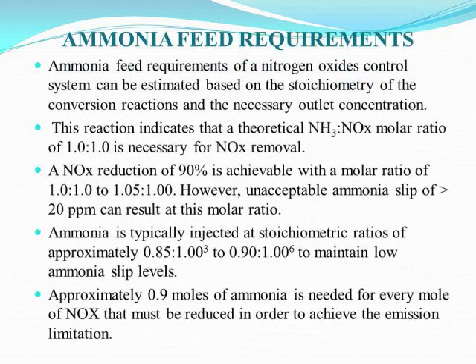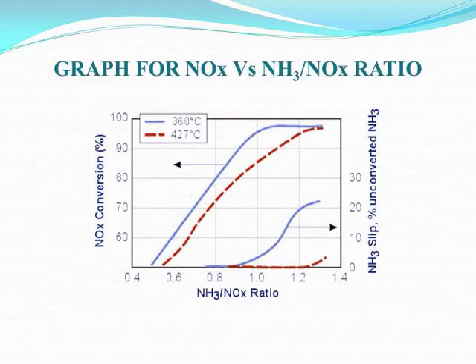Regarding dilution of ammonia: following vaporization, the reagent is emitted into a dilution carrier gas stream to keep the ammonia concentration below the explosive range and to facilitate mixing into the gas stream. The ammonia concentration of the gas stream injected upstream of the SCR bed is usually 3 to 5% by volume.